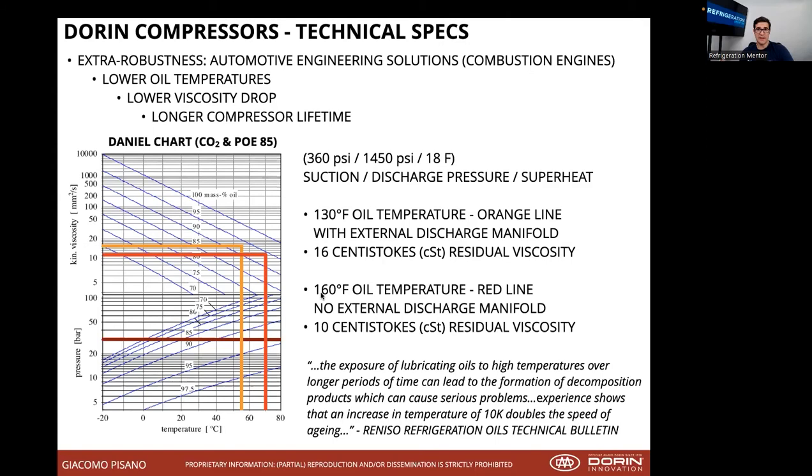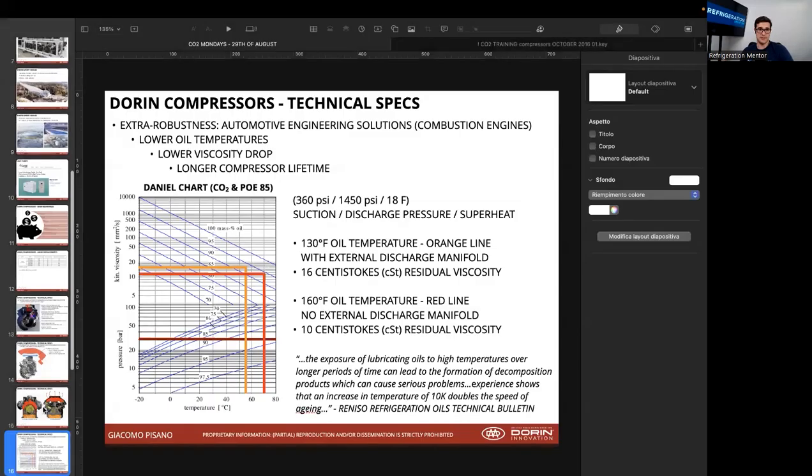Compressors are designed for long life, but you have to properly install, service, and maintain them. If you're not maintaining a system, temperature can climb up quickly. When you have a compressor that already runs at lower temperatures, you get a little extra cushion — but you still need to be maintaining these systems properly. That lower oil temperature from the external plenum gives you lower oil temperature, and that's really what the plenum does. Do you have some sort of electronics that monitor discharge temperature or oil sump temperature in your compressors? We do offer a high temperature probe that stops the compressor when it exceeds 160°C (320°F), and it is an internal probe within the plenum, wired back to the control module.